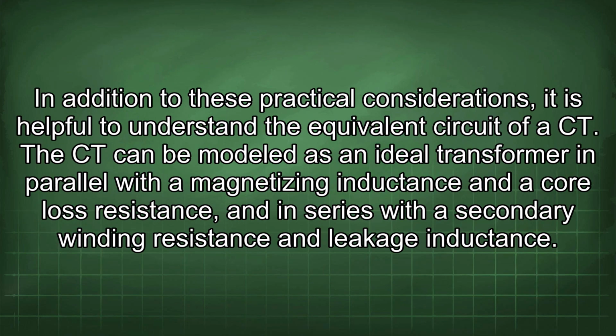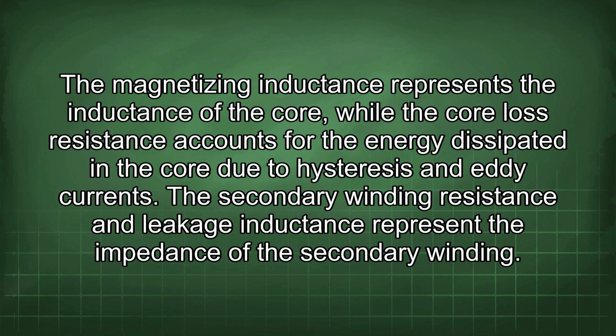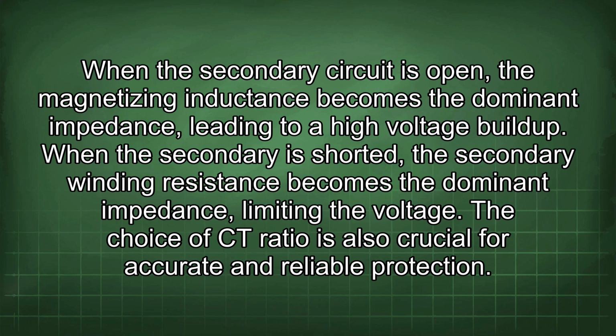In addition to these practical considerations, it is helpful to understand the equivalent circuit of a CT. The CT can be modeled as an ideal transformer in parallel with a magnetizing inductance and a core loss resistance, and in series with a secondary winding resistance and leakage inductance. The magnetizing inductance represents the inductance of the core, while the core loss resistance accounts for the energy dissipated in the core due to hysteresis and eddy currents. The secondary winding resistance and leakage inductance represent the impedance of the secondary winding. When the secondary circuit is open, the magnetizing inductance becomes the dominant impedance, leading to a high voltage buildup. When the secondary is shorted, the secondary winding resistance becomes the dominant impedance, limiting the voltage.